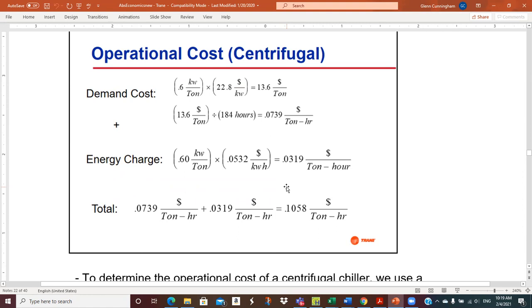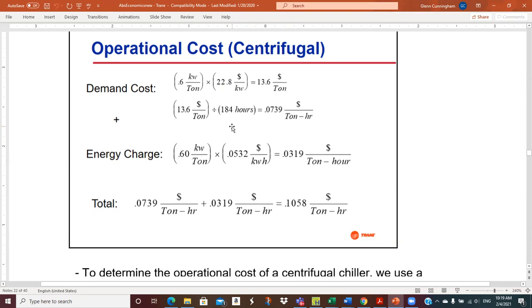Okay, so if it's 0.6 kW per ton, and we're charged demand charges per kW, so the charge is $22.80 for that on-peak period when it's the max demand. So it's $22.80 times 0.6, so we get $13.60 per ton. And now, okay, he's going to spread this out over these 184 hours. So you need to.